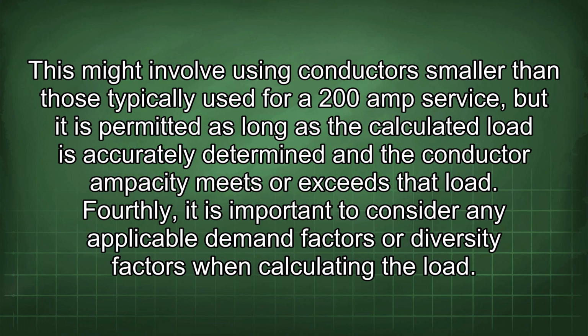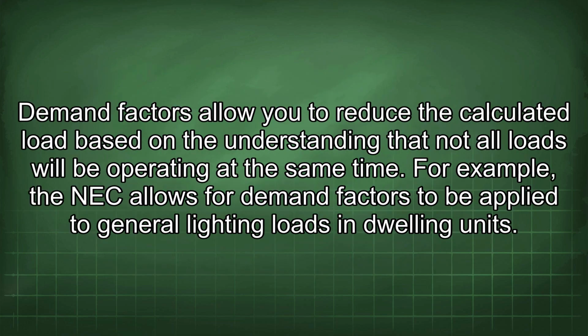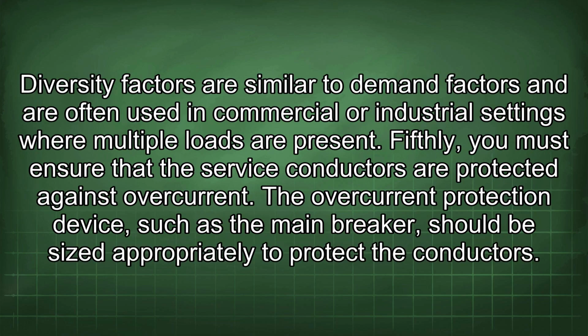Fourthly, it is important to consider any applicable demand factors or diversity factors when calculating the load. Demand factors allow you to reduce the calculated load based on the understanding that not all loads will be operating at the same time. For example, the NEC allows for demand factors to be applied to general lighting loads in dwelling units. Diversity factors are similar to demand factors and are often used in commercial or industrial settings where multiple loads are present. Fifthly, you must ensure that the service conductors are protected against overcurrent.